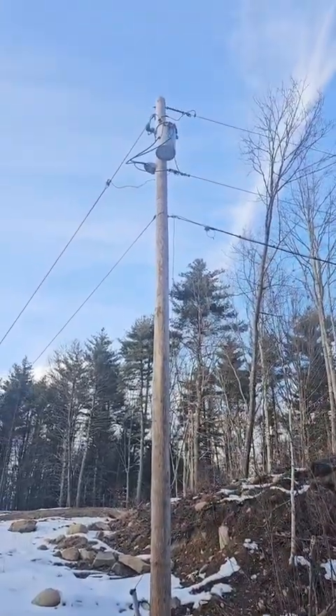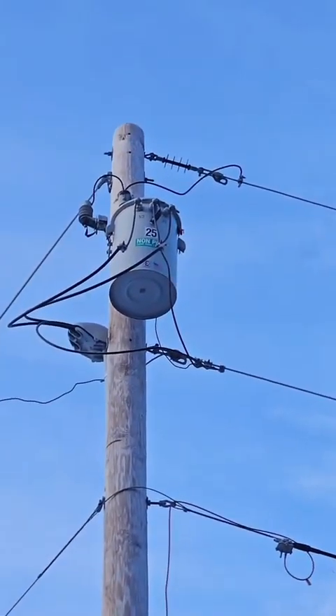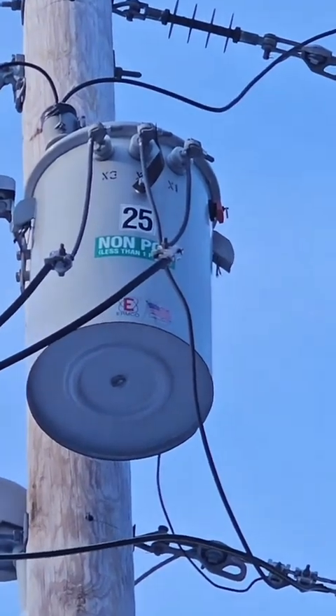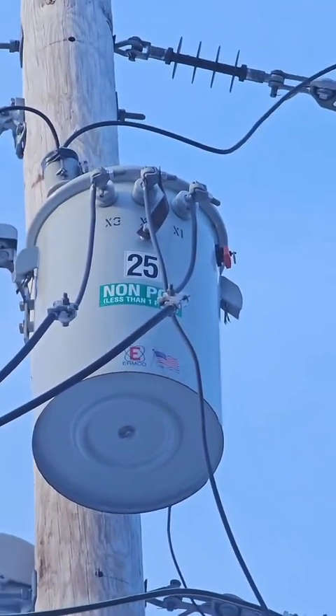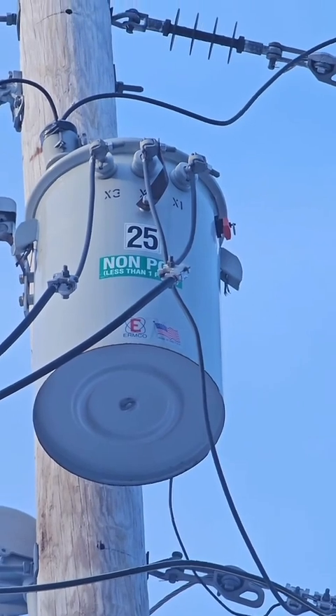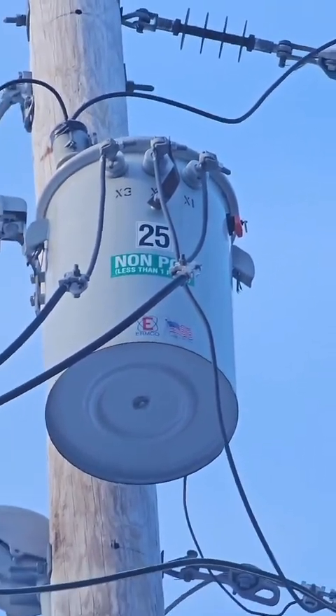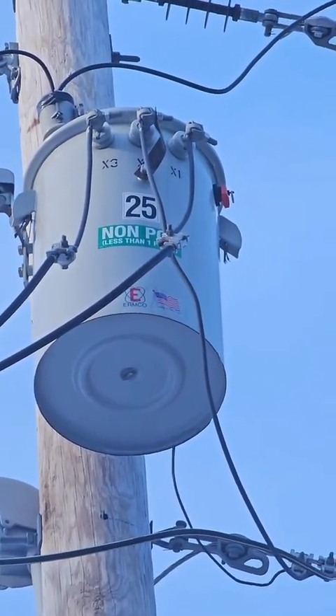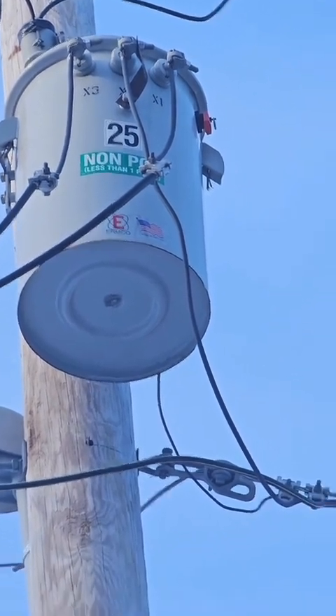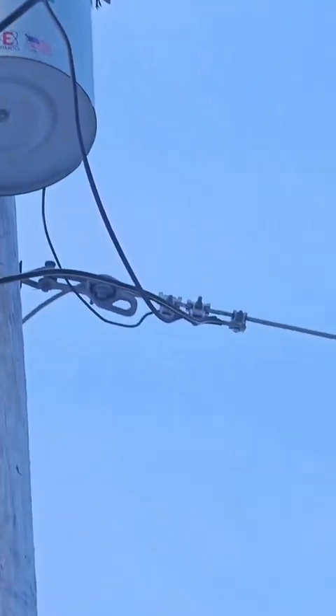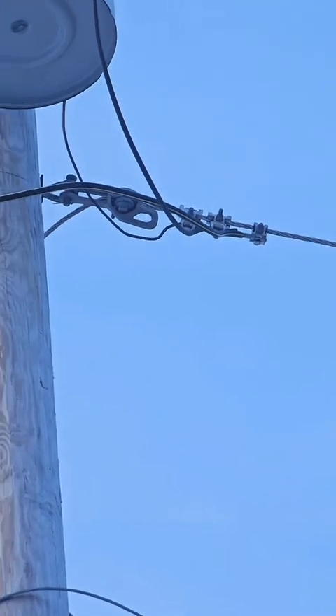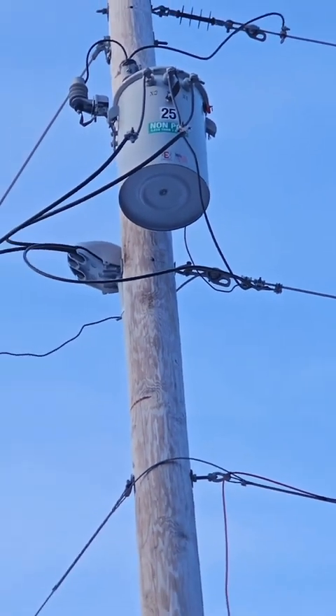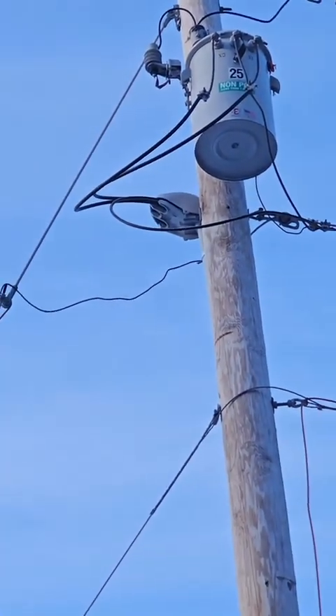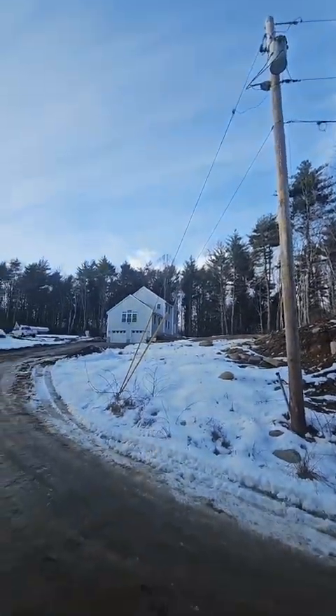All right, now let's look at those connections on the transformer end. So the transformer has those three connections. The two outer ones are the hot wire, the two hot wires. That middle one is the neutral. You can see how it jumps from that center pin to the can. So that's ground in the can, or bond in the can. And then we follow it, it goes to here, which now if we zoom out, after it comes off there, one goes down that weatherhead to my house right there. And the other one on the back side connects to that guy wire, which then goes down into the earth.